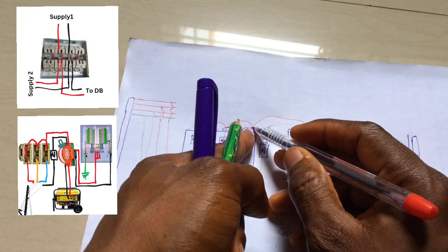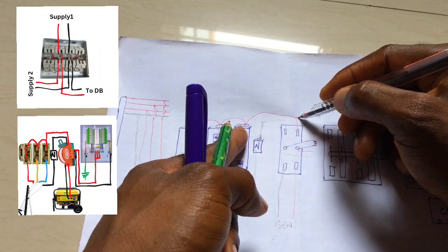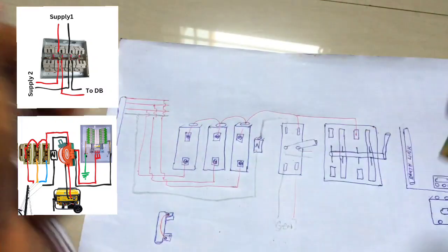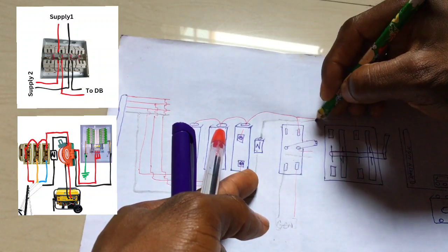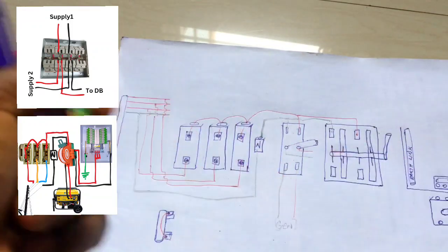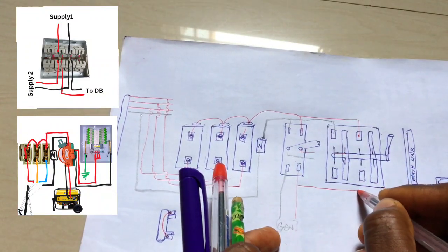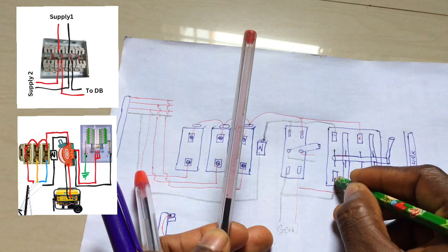Now let's assume we are making use of the gear changeover. From the public grid supply, live comes to this input point, and we equally pick the neutral here — this is the first source. If we are using a generator or any other alternative source, we do the same — loop live and neutral for the generator input. These output points go to our building.